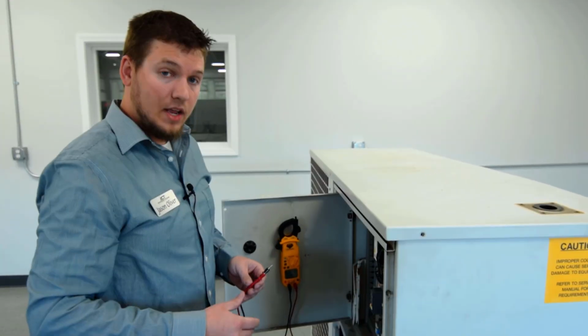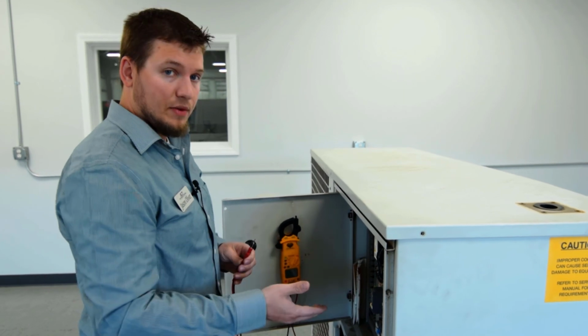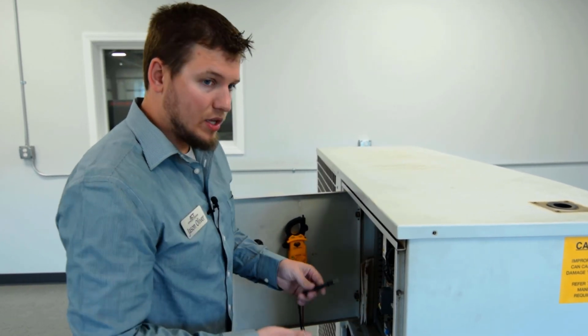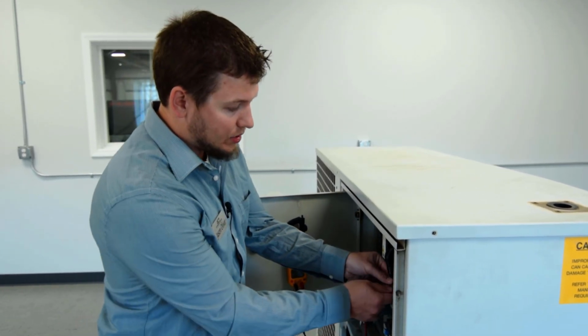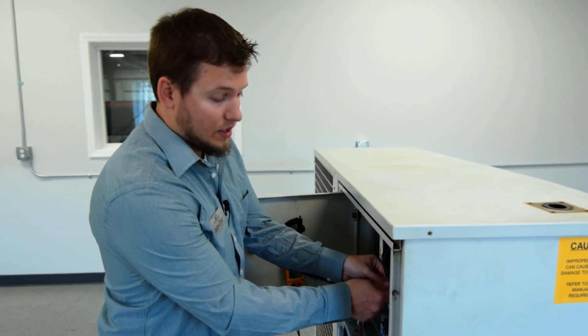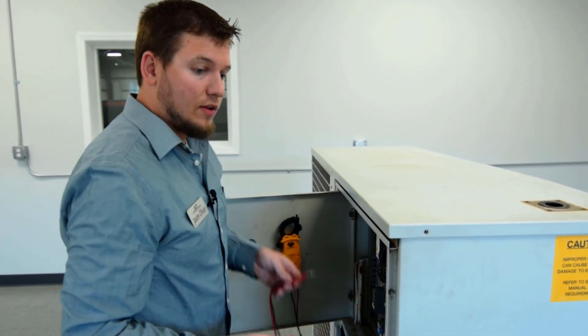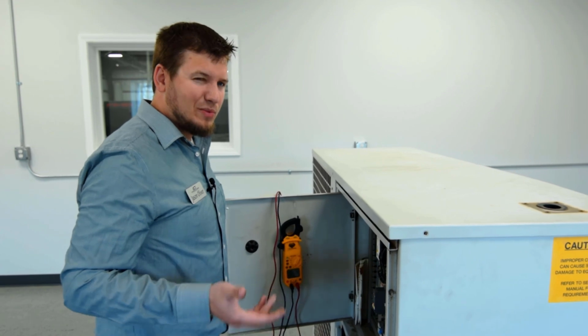The next step is to verify the incoming voltage to the chiller. The best way to do this is take your probes and go L1 to L2, L1 to L3, and then L2 to L3. You're going to be looking for roughly 480 volts plus or minus 10%.